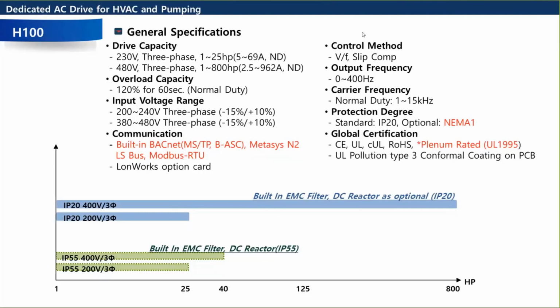So if you look at the top right here, you can see that the H100 is rated up to 800 horsepower for 480 volts, and then 25 horsepower for 230 volts. And also notice there's that ND, so that's normal duty. So this is a normal duty drive. It's 120% overload for 60 seconds. And once we get to the larger drives, it's 110% overload for 60 seconds. So this is meant for variable torque applications, which typically require that lower overload capacity. So there's no selectability on the H100.